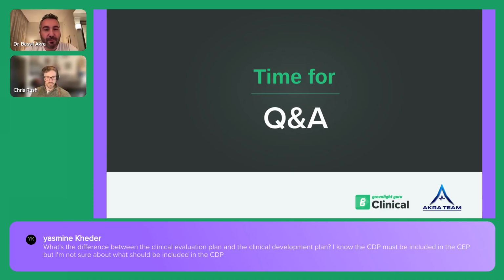So the clinical evaluation plan is actually the holistic plan for your clinical evaluation, which means what is the intended use, what are the claims, what are my criteria to show safety and performance, which strategy I'm going to follow to do a clinical evaluation. Whereas the clinical development plan is focusing on the way how you're going to collect data.